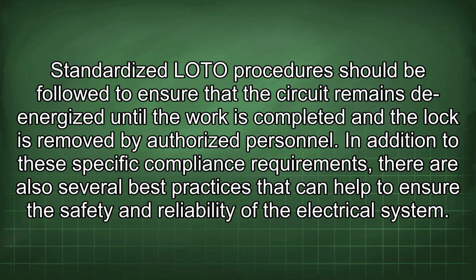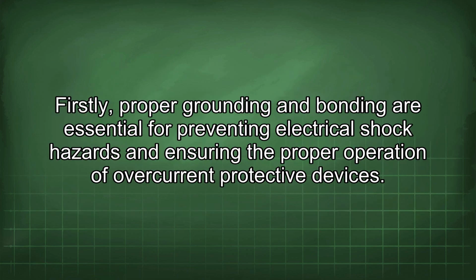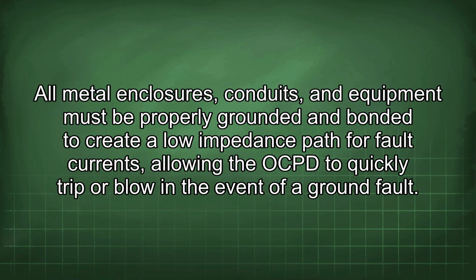In addition to these specific compliance requirements, there are also several best practices that can help to ensure the safety and reliability of the electrical system. Firstly, proper grounding and bonding are essential for preventing electrical shock hazards and ensuring the proper operation of overcurrent protective devices. All metal enclosures, conduits, and equipment must be properly grounded and bonded to create a low impedance path for fault current, allowing the OCPD to quickly trip or blow in the event of a ground fault.